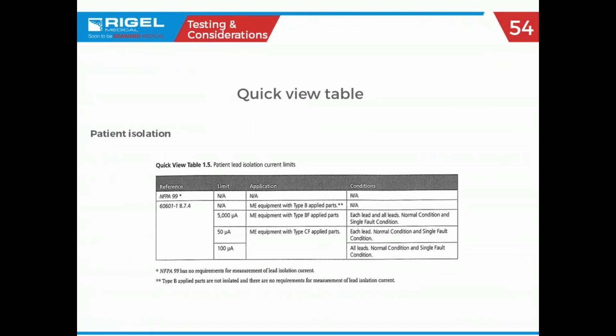Patient isolation, or isolation testing. This is where you put a voltage on your applied parts or onto the device. 60601 says you put mains on your applied parts and such. NFPA 99 says you don't have to do that.